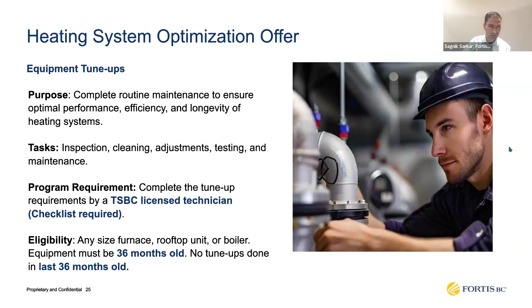In the next slide, we will see the boiler optimization measures. The purpose of boiler optimization measures, especially for hydronic systems, is to improve your existing hot water system. I'll be using the term boiler and hot water heater interchangeably because most MURBs do not use steam, mostly using hot water for circulating and hydronic heating.